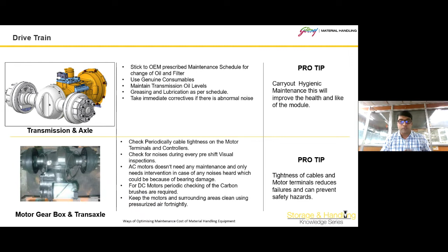Always try to keep the motor compartment clean, because any dust entering inside can destroy or damage your rotors as well as your armatures. So keep it clean. Use pressurized air once a week, in the weekly inspection or weekly maintenance schedule. If your compartment is very clean and no dust goes inside the motor, it will work perfectly and you will get the most life out of your motor.